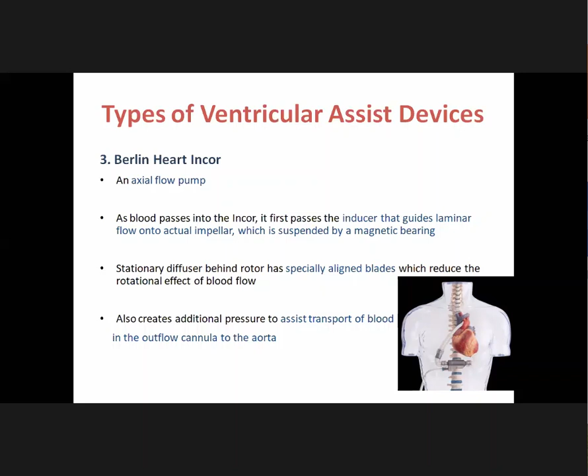The advantage of this system is that they have a magnetic bearing which helps in better transmission of blood through the outflow conduit. The stationary diffuser behind the rotor has specifically aligned vanes which reduce the rotational effect of the blood flow and also create additional pressure to assist transport of blood into the outflow cannula to the aorta.